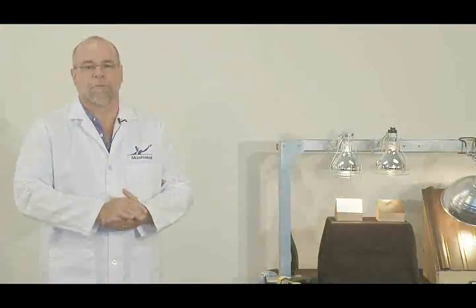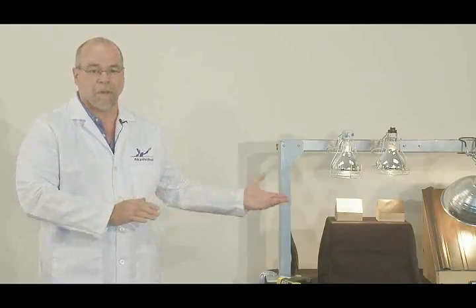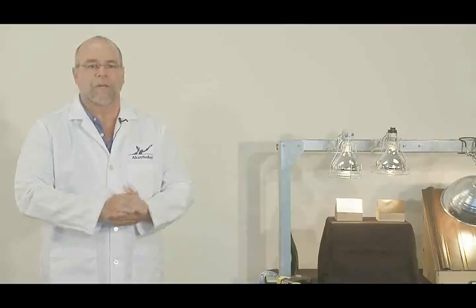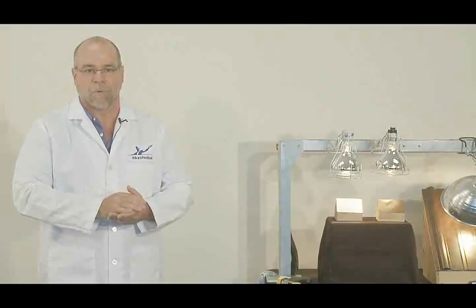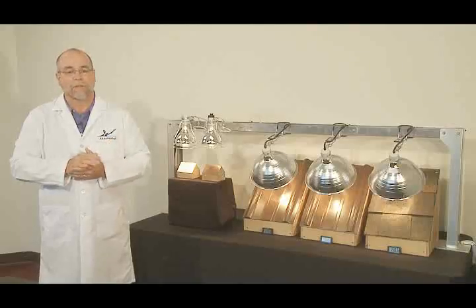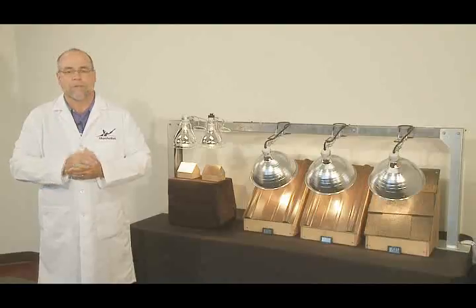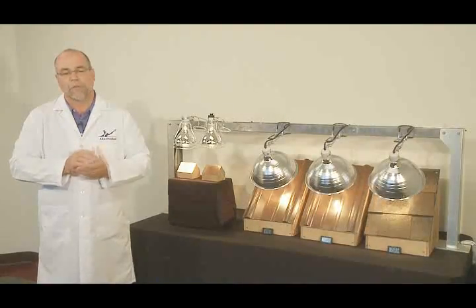The first demonstration we will do is between a Cool Chemistry series white and a standard pigmentation dark brown metal roof. The white sample on the left has a solar reflectance of 0.72, which means that of all the solar energy that hits the surface, 72% of it is reflected away and never absorbed. The dark brown sample on the right has a solar reflectance of 0.13, which means that only 13% of the solar energy is reflected. We'll give the metal a few minutes to heat up, and then we can measure the temperature of each.